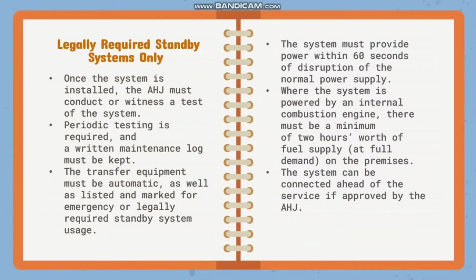So, legally required standby systems only. These are requirements for legally required standby systems. Once the system is installed, the authorities having jurisdiction must conduct or witness a test of the system. Next, periodic testing is required and a written maintenance log must be kept. The transfer equipment must be automatic as well as listed and marked for emergency or legally required standby system usage.